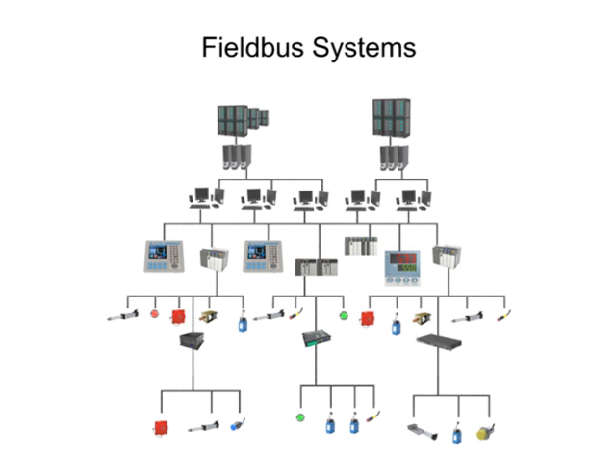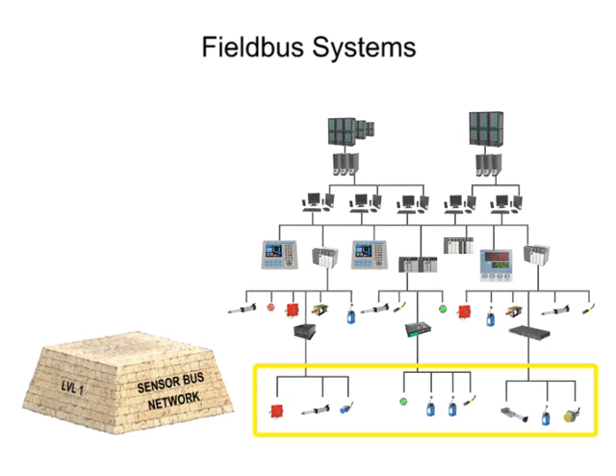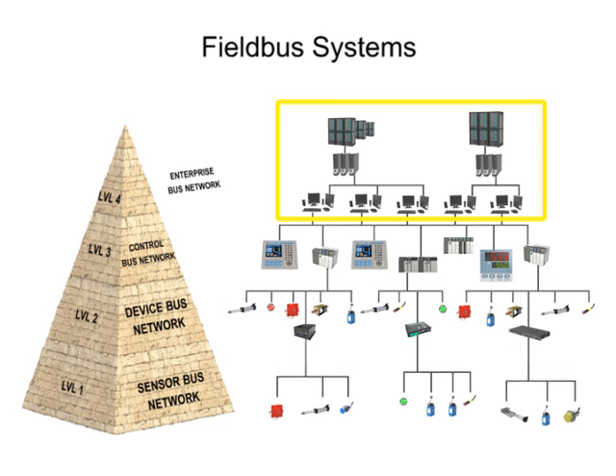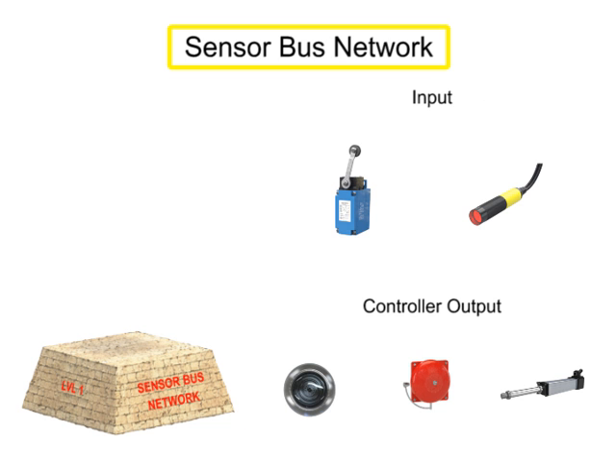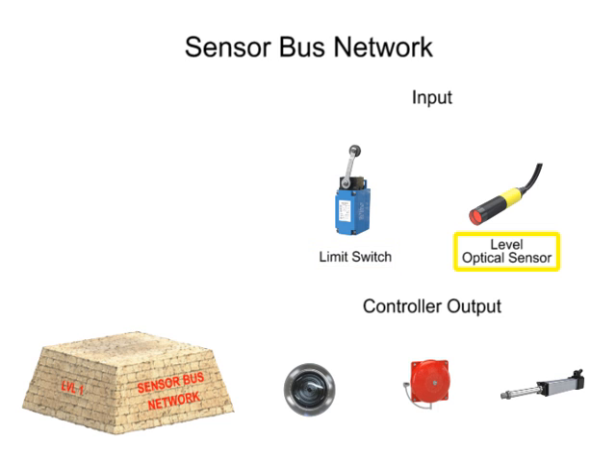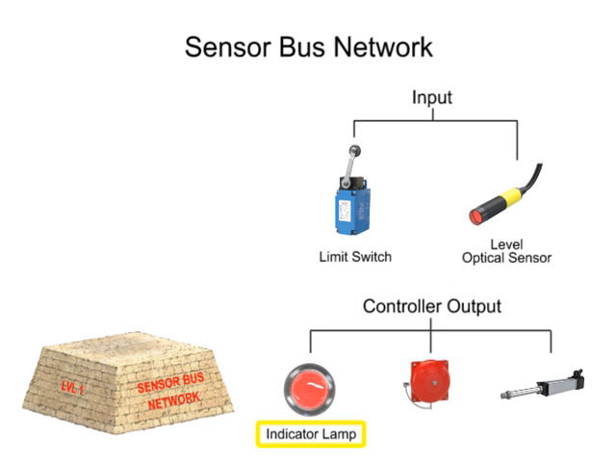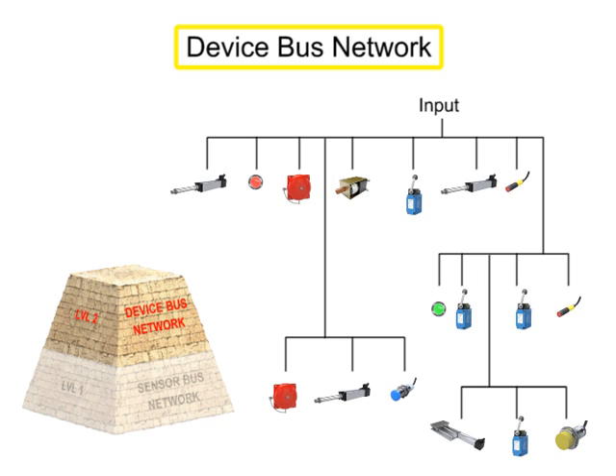Fieldbus industrial networks can be broken down into four levels, each with increasing levels of complexity. The most basic level is the sensorbus network. Sensorbus networks are the least complex networks developed for industrial application. In these networks, multiple basic field devices like limit switches or optical level sensors are connected to one network cable. The sensorbus network is also capable of transmitting output signals from the controller over one cable to indicator lamps, alarms, or other actuator devices.